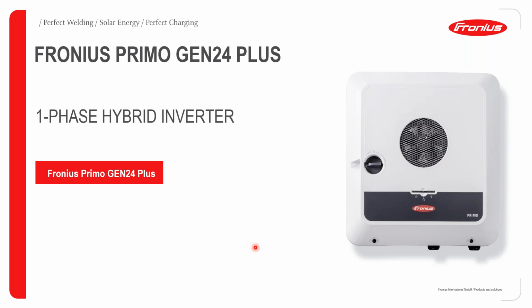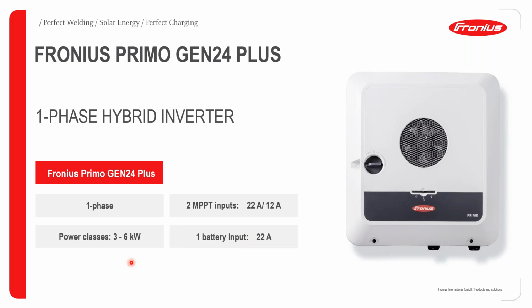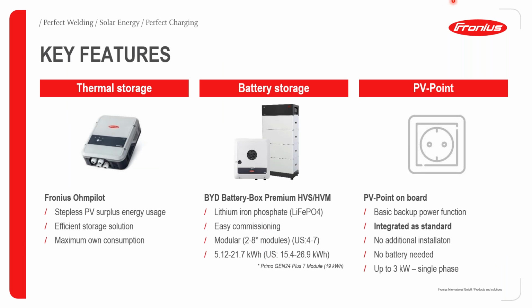The single phase Gen 24 Plus inverter also comes with 2 MPPTs. 1 MPPT can be connected up to 22 amps of current, and the other one can take up to 12.5. Power classes are available from 3 to 6 kilowatts. And it also comes with a battery input, similar to the Symo Gen 24 Plus, of up to 22 amps. So it is also available starting Q1 of 2021.